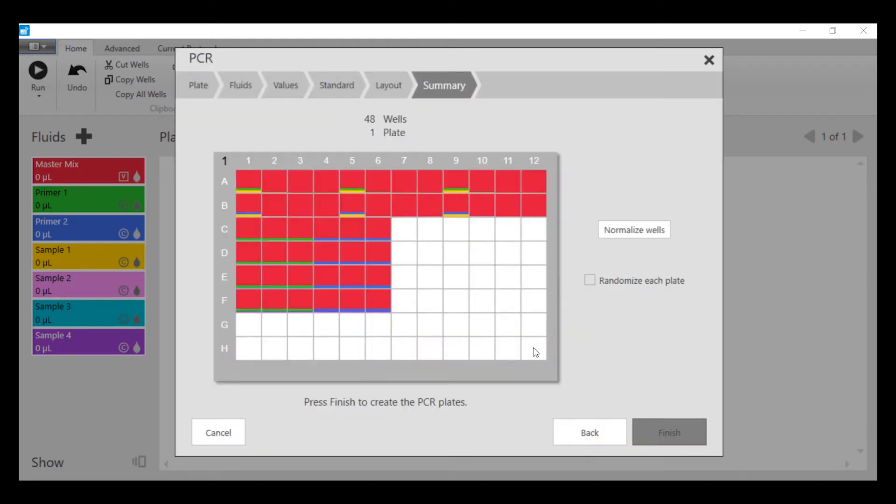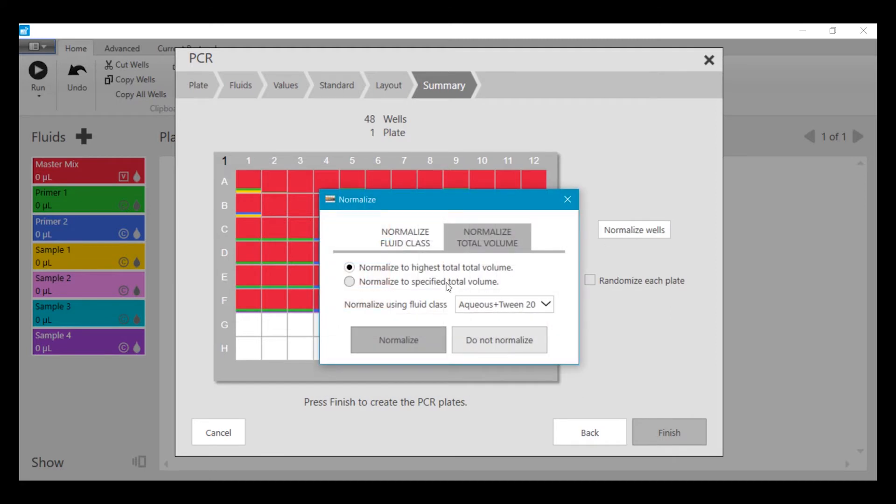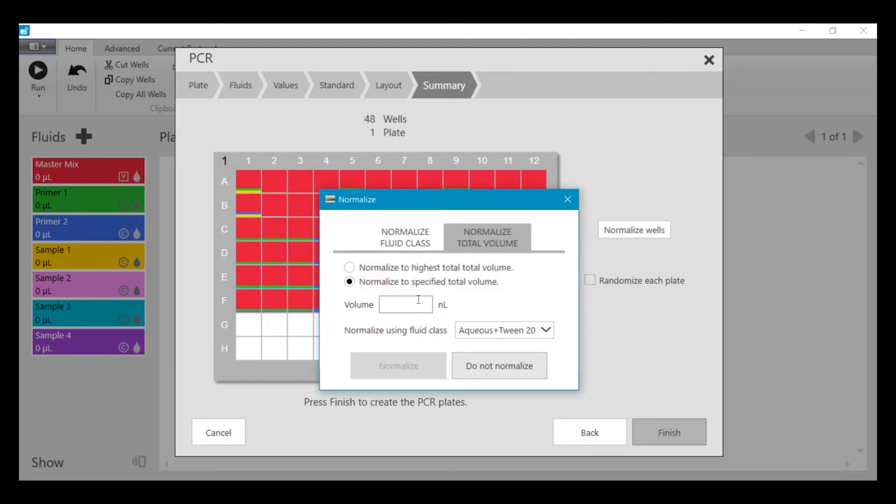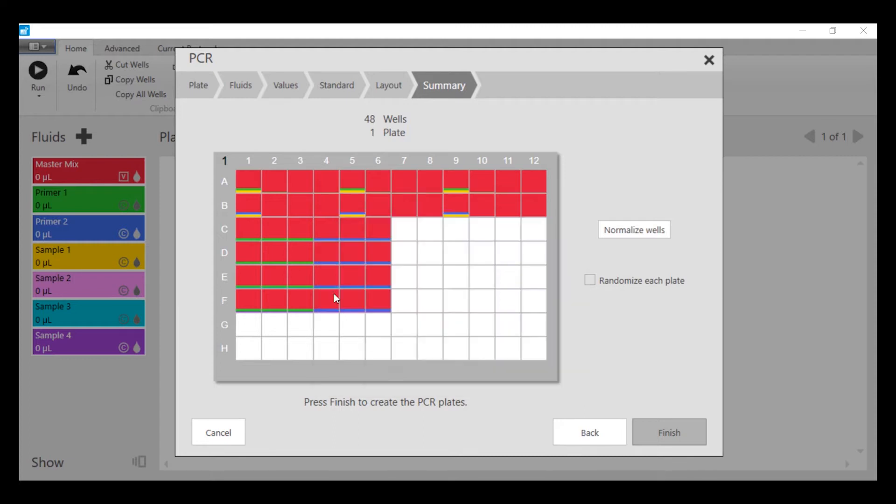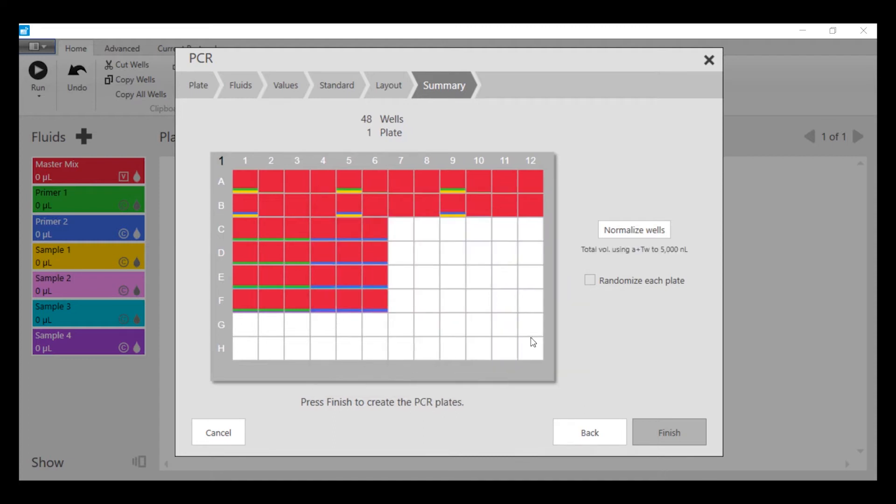That's set up properly, and now it's laying out the plate for us, showing the various amounts of fluid in each well. In this case, we're going to normalize these wells. We're going to normalize it to a 5 microliter total assay volume, every well 5,000 nanoliters. And the reason we're doing that is because the samples were different concentrations to begin with, and so we're normalizing the concentration of RNA or DNA in each well. And you didn't have to do that by hand separately as you would have had to do normally.